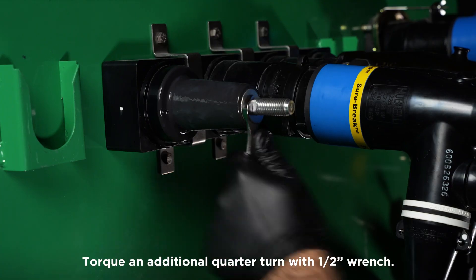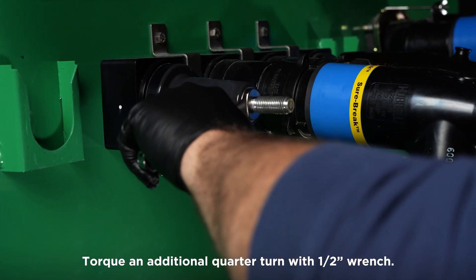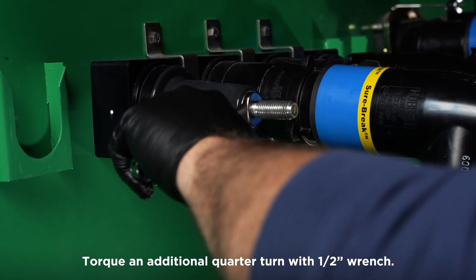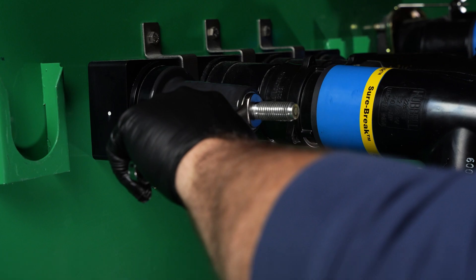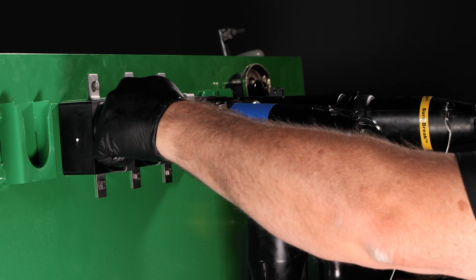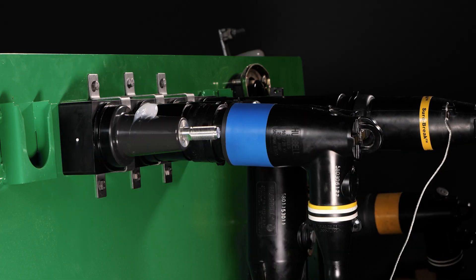After the stud is installed hand tight, torque the stud another quarter turn with a one-half inch wrench to secure it. The SureTap and T-body are ready for installation.